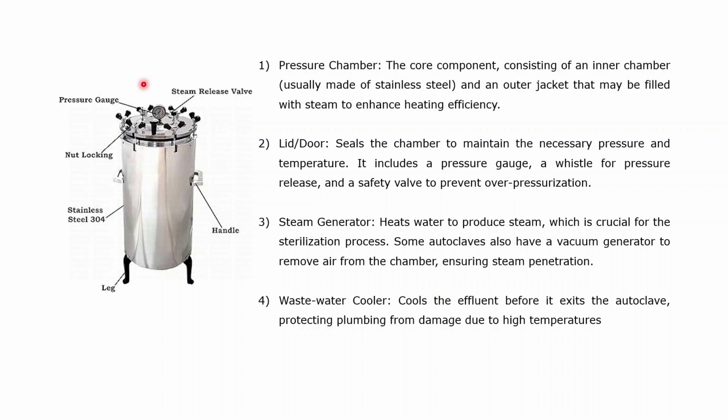So once the sterilization has completely taken place, you switch off the autoclave, leave it for like 10 to 15 minutes, then you open the valve there. There's actually a steam release valve there. You can see that in this case. It can be at the top or at the bottom, it depends. Once it is released, the steam goes out, and the pressure comes down as well as the temperature, and afterwards you just open it up, keep it open for some time so that the excess steam gets out of the autoclave, and then you take the materials out after the proper sterilization. So these are the basic components of an autoclave.